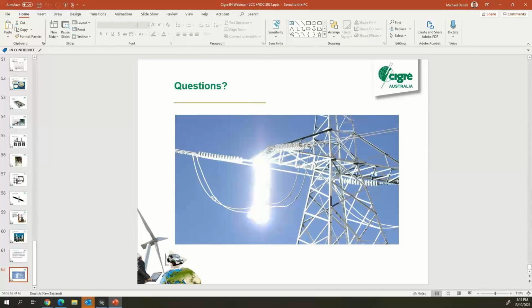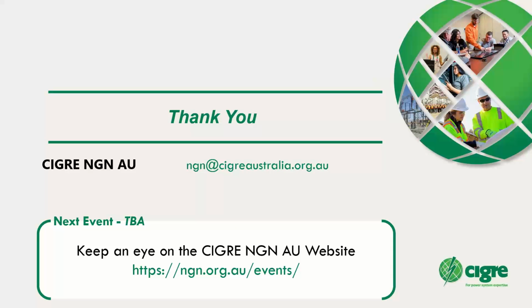Yeah, I meant without a metallic return. Sorry, I was just wondering, can you operate the link if one of the cables failed as a monopole? I presume you can. Yes, of course. Say we had one of the cables fail. We've actually got 3 cables: 2 cables on pole 3 and 1 cable on pole 2. So if we did have a cable fail on pole 3, we'd operate on pole 2 as a monopole, utilizing the ground return 100%. Then we would switch the failed cable off pole 3, and then we could turn pole 3 back on with just 1 cable. That would limit us to 1,000 megawatts instead of 1,200, which isn't too much of a big deal, really. So a single cable failure is not too bad for our scheme. But if we had another one, that would be quite major, because then we'd be down to monopole and we'd be limited at 500.